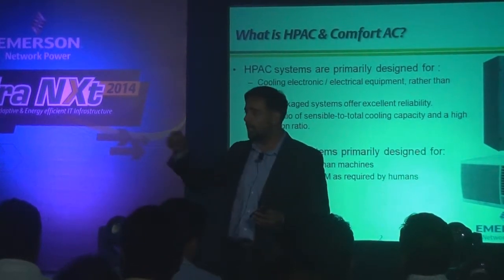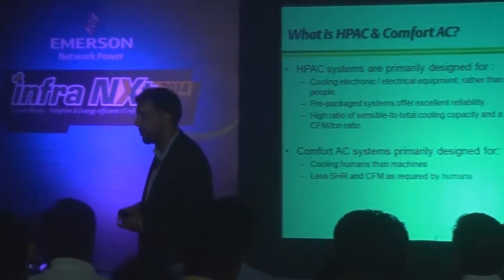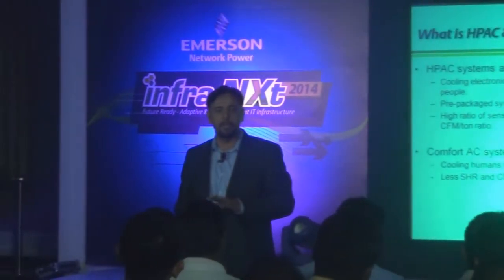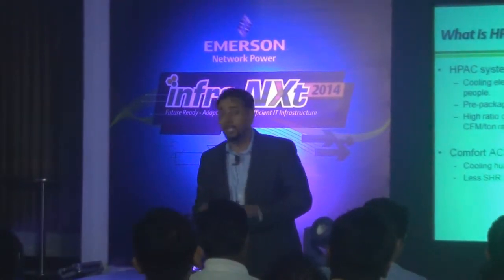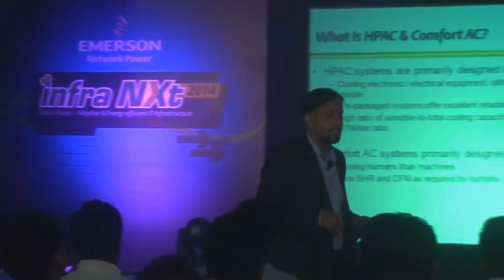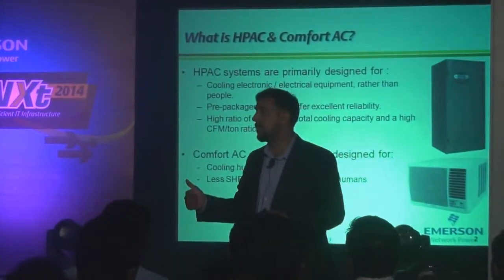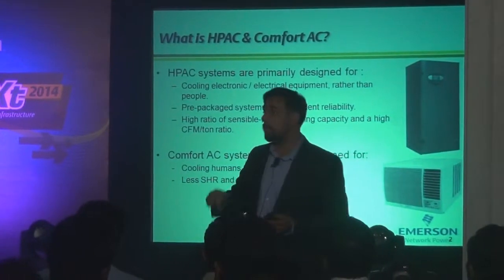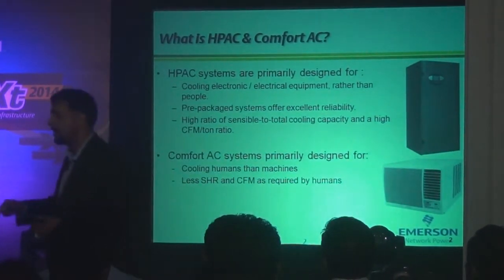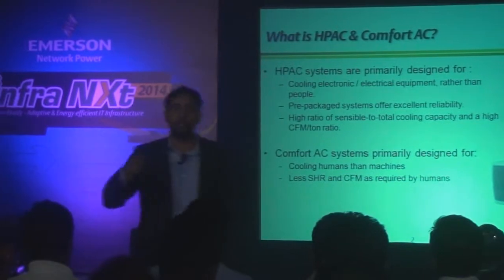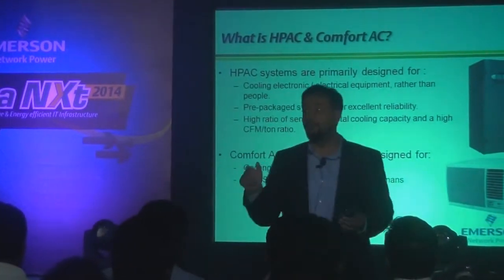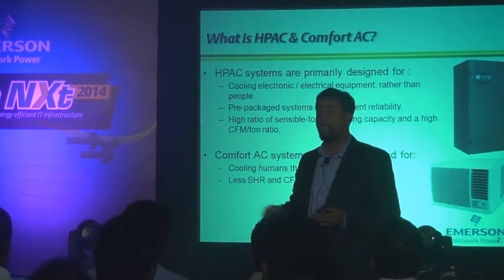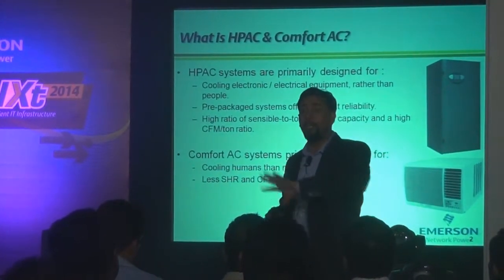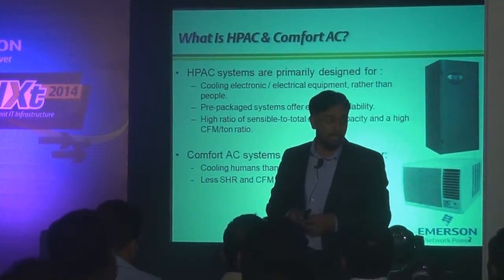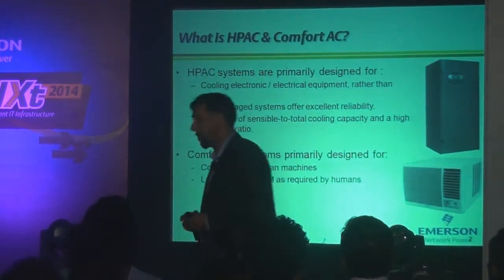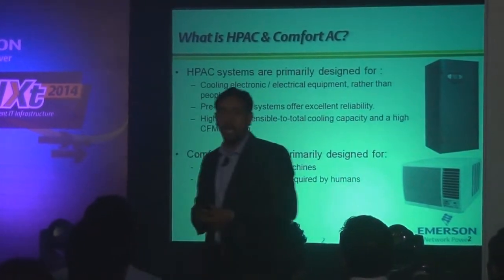To remove this total heat we require an air conditioning system. The basic difference between comfort and precision AC is that electronics rooms like server rooms, data centers, switch rooms, and telecom shelters only have equipment, and equipment only dissipates heat—it doesn't sweat or add moisture to the room. So we only have sensible load in such applications, and we need to remove only the sensible load, not the latent, comfort part.